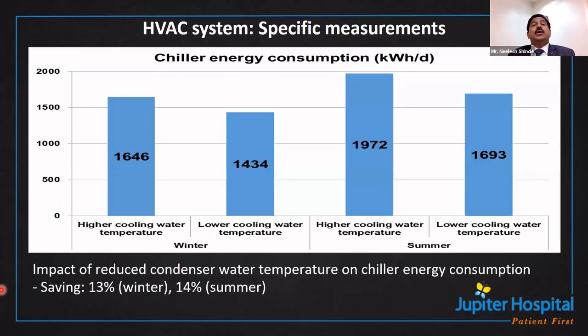Now this is very important. If you see here, some figures have been shown, this is winter, this is summer. For chiller energy consumption, condenser water we used to keep around 27-28 degrees as inlet and 32 as outlet. We used to get around 1646 units against 1972 units. This is per day consumption.